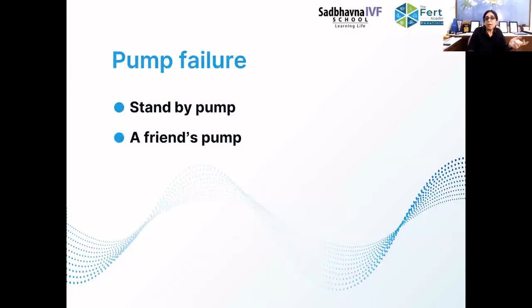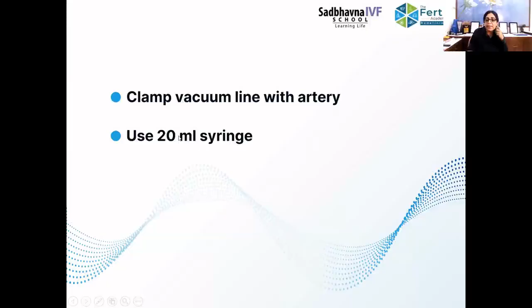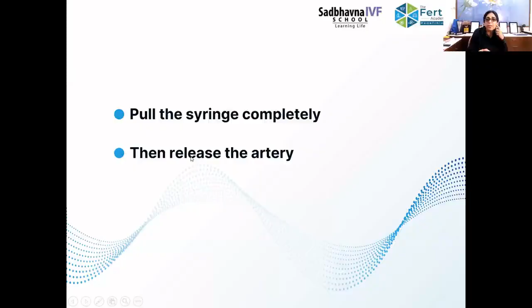Other than that, what can you do? This is a very simple, you could say life-saving procedure for the oocyte if you don't have an extra pump. What you do is clamp the vacuum line with an artery forceps. The vacuum line is the one going to the pump. Use a 20 ml syringe and pull the syringe completely to create negative pressure. Then release the artery and the follicular fluid is aspirated.